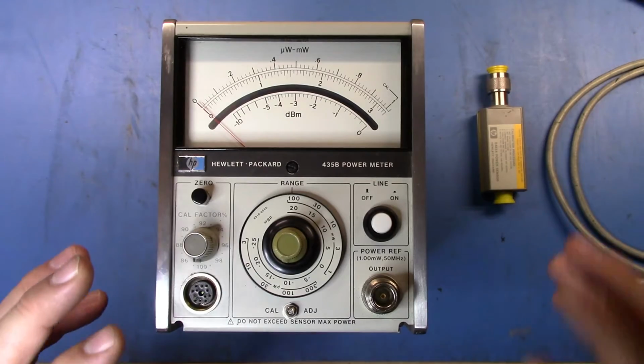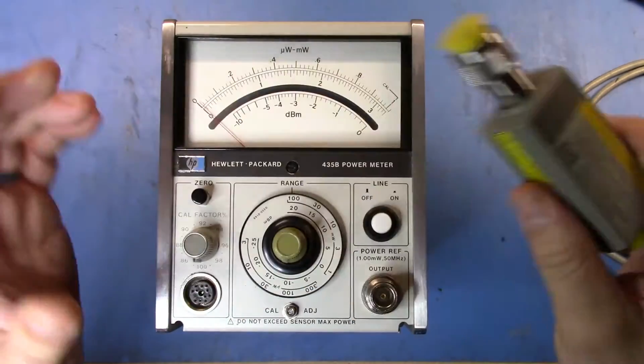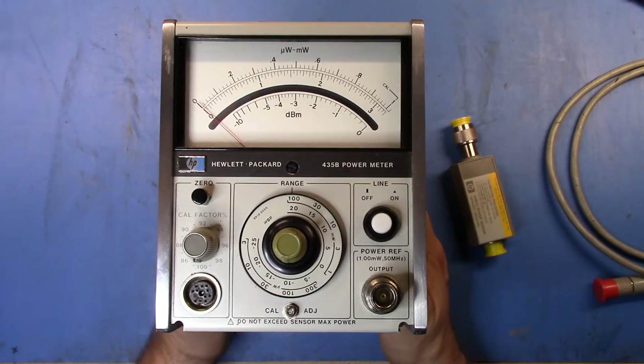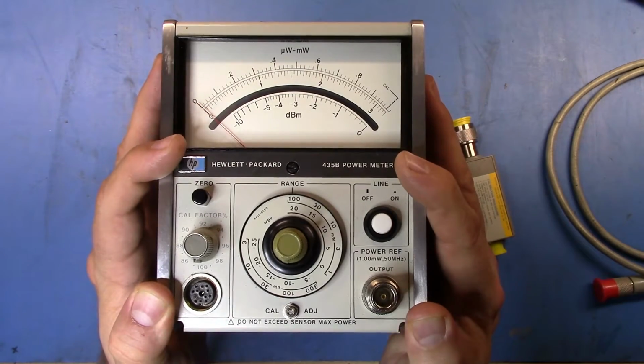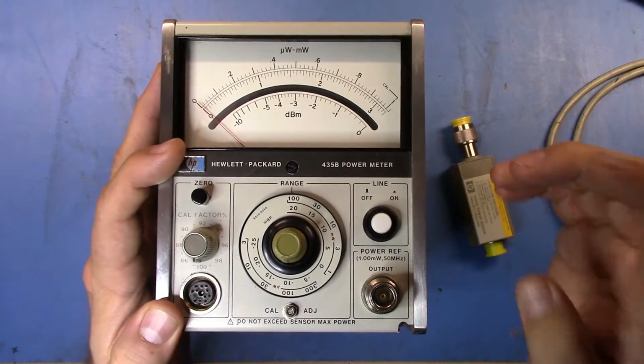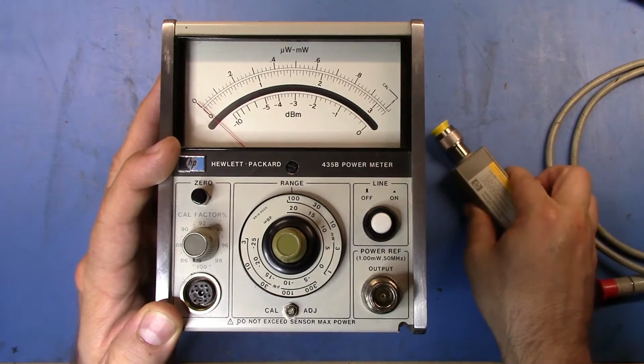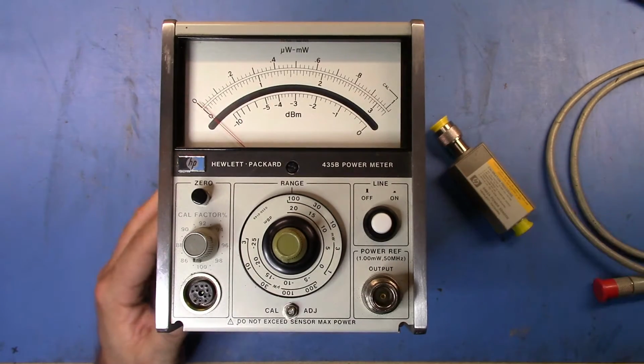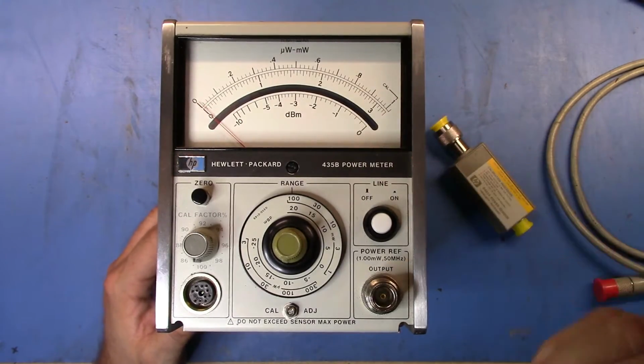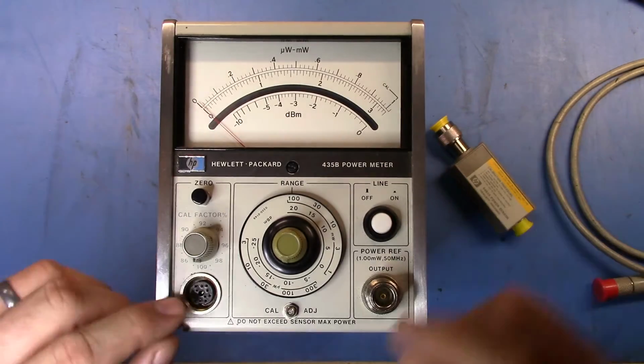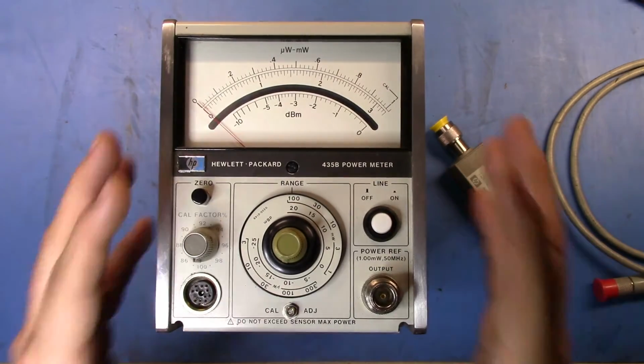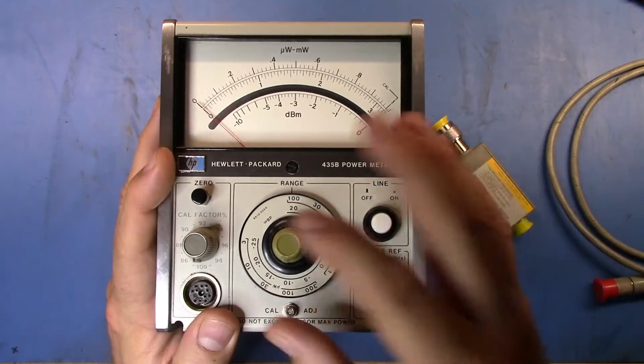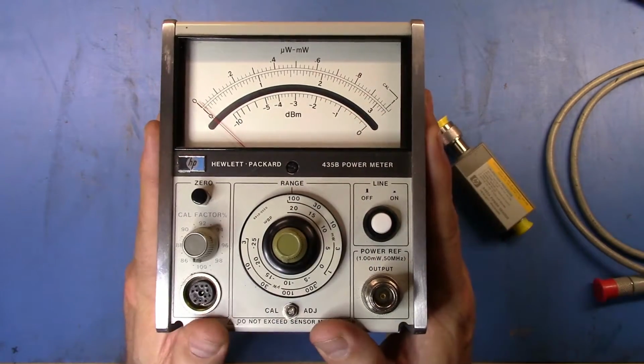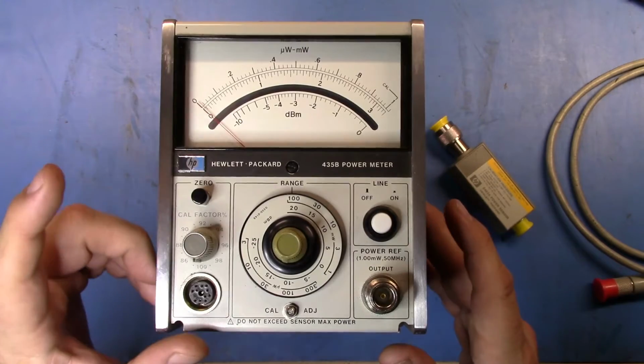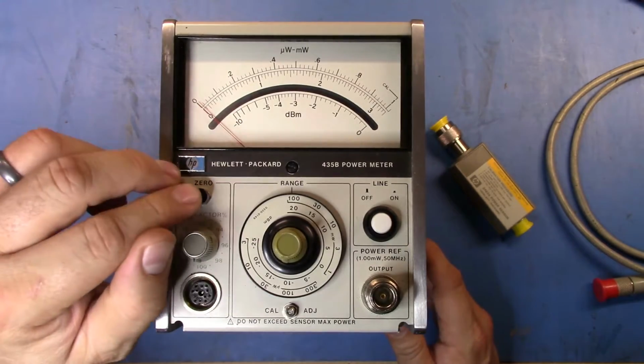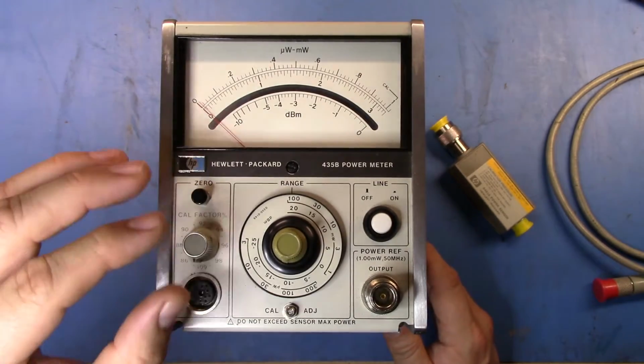But these little thermocouple sensors were removed from the 432s, which is the other meter prior to this that used a thermistor. These used a thermocouple. And the basic idea is that you put RF power into the thermocouple that creates a DC offset that can be then read by this meter. And you can calibrate the whole thing. So on the front here, what we see is the sensor connection. We see a 0 button and a calibration factor.